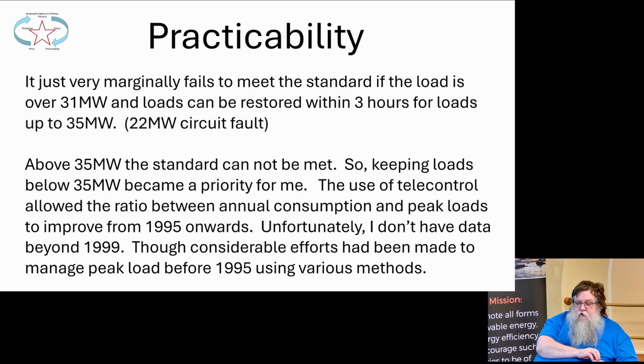But again, if it just marginally fails to meet the requirement, you can look at the cost and say it's going to cost £1 million or £10 million or whatever, and it's only a small failure, and that small failure is also for a very short period of time. So you take a risk-based approach and you don't do anything. But above 35 megawatts, the standard cannot be met.